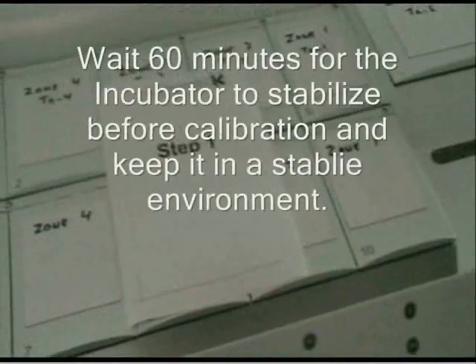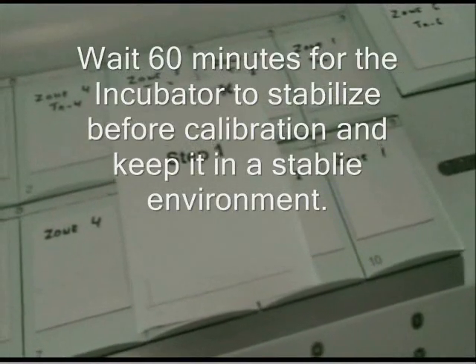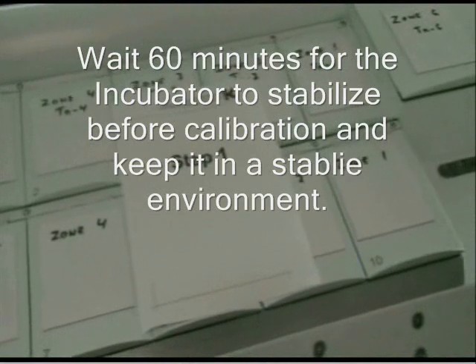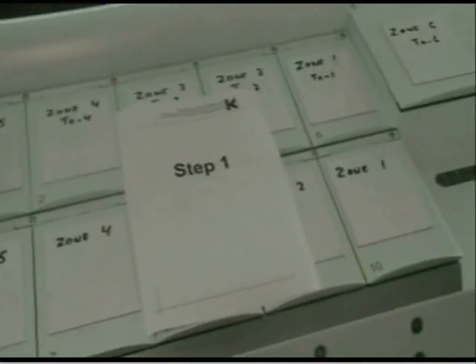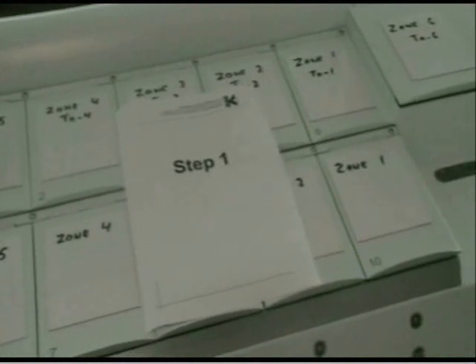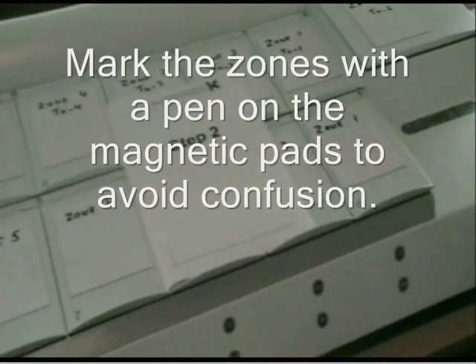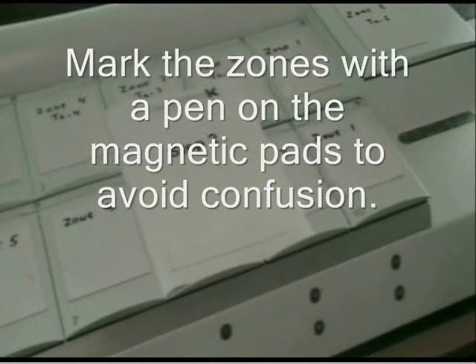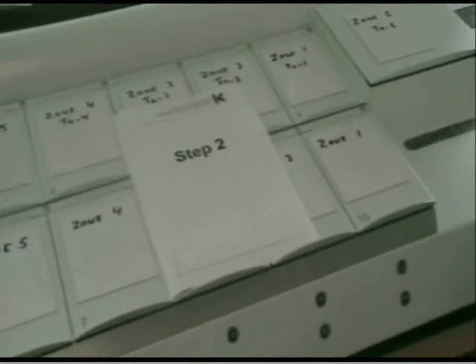When any calibration is attempted, make sure that the incubator has been running for at least 60 minutes to stabilize the temperature. Make sure that it's in a stable environment, and it should preferably be where it's intended to be used. Mark out the temperature zones on the magnetic pad lids, and also the zone numbers. This you do in order to not get confused later on when we do the actual calibration inside the menu.